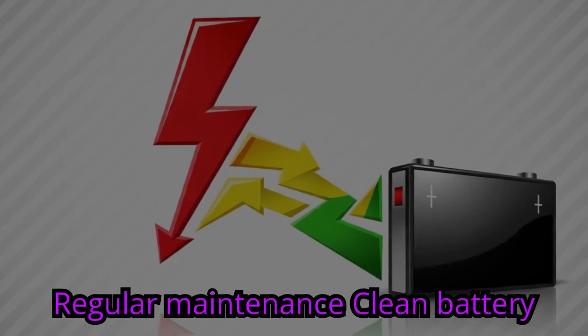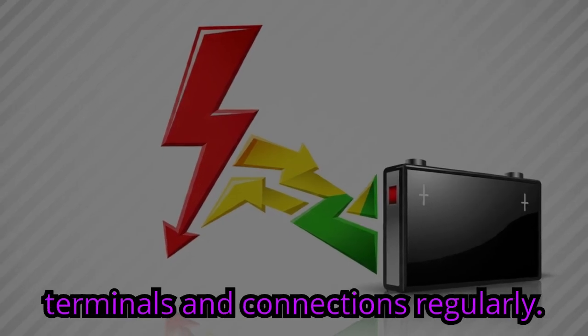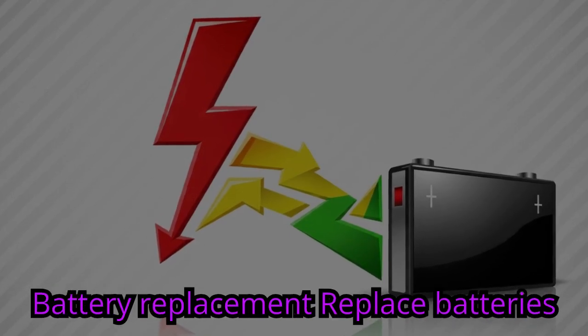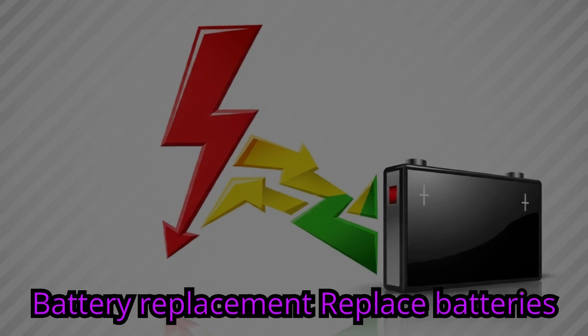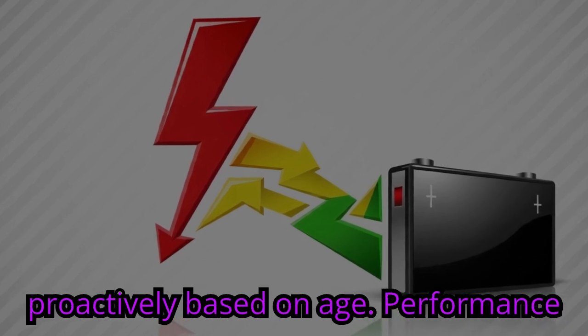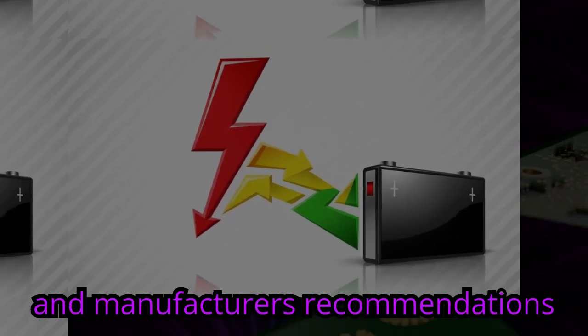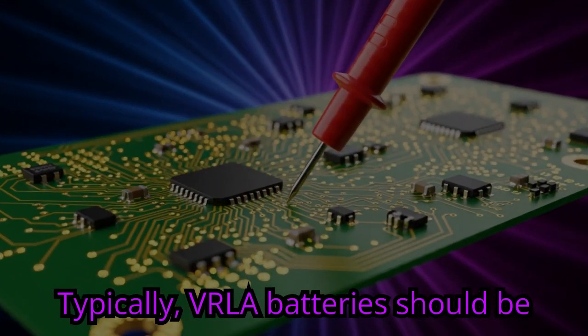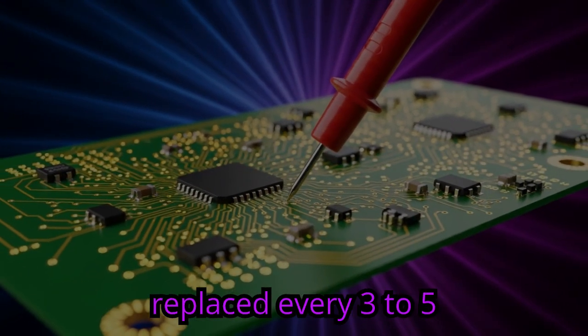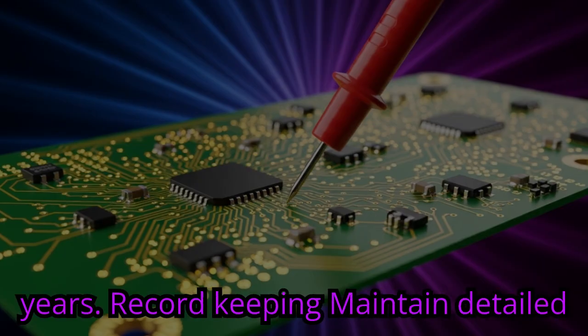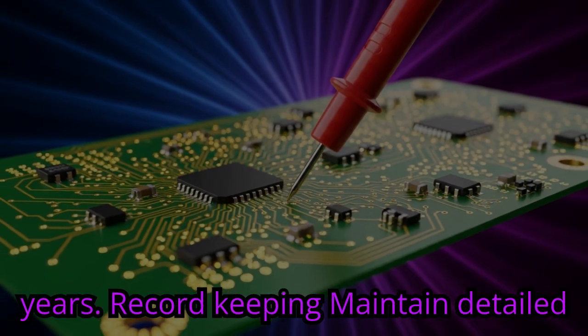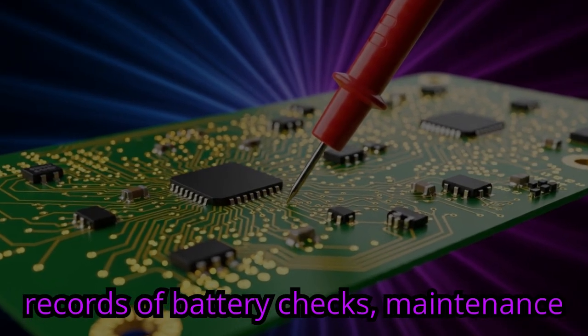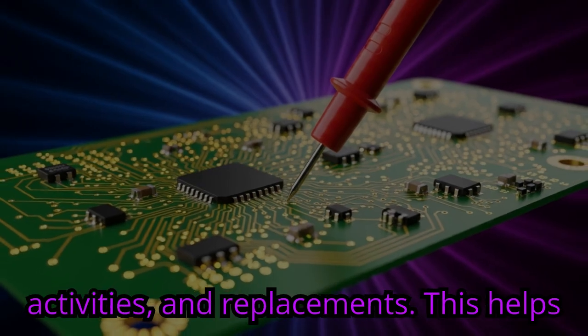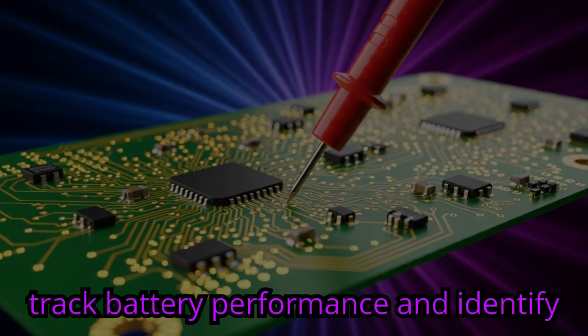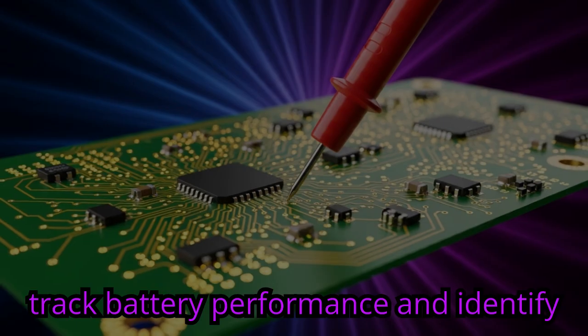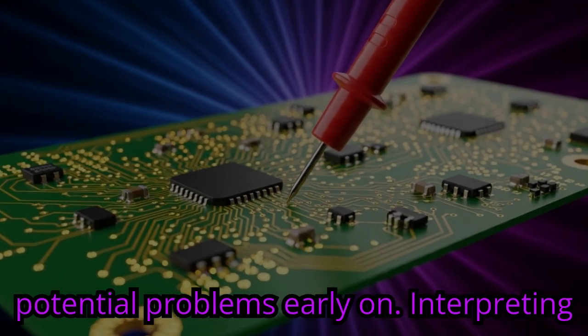Regular maintenance. Clean battery terminals and connections regularly. Battery replacement. Replace batteries proactively based on age, performance, and manufacturer's recommendations. Typically, VRLA batteries should be replaced every 3 to 5 years. Record keeping. Maintain detailed records of battery checks, maintenance activities, and replacements. This helps track battery performance and identify potential problems early on.